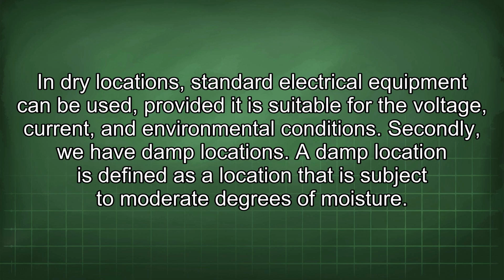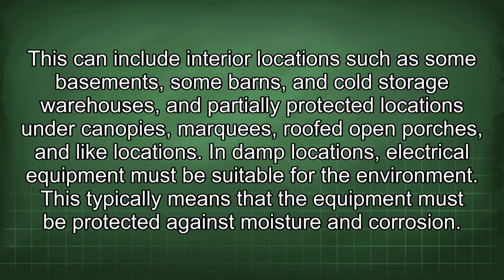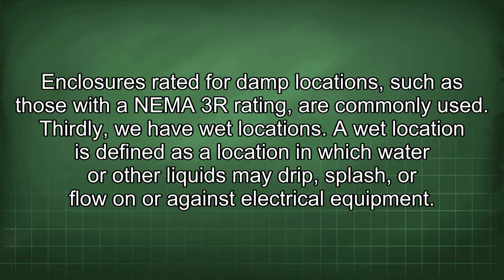A damp location is defined as a location that is subject to moderate degrees of moisture. This can include interior locations such as some basements, some barns, and cold storage warehouses, and partially protected locations under canopies, marquees, roofed open porches, and like locations. In damp locations, electrical equipment must be suitable for the environment. This typically means that the equipment must be protected against moisture and corrosion. Enclosures rated for damp locations, such as those with the NEMA 3R rating, are commonly used.